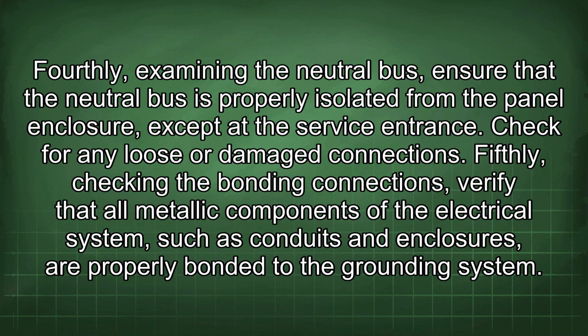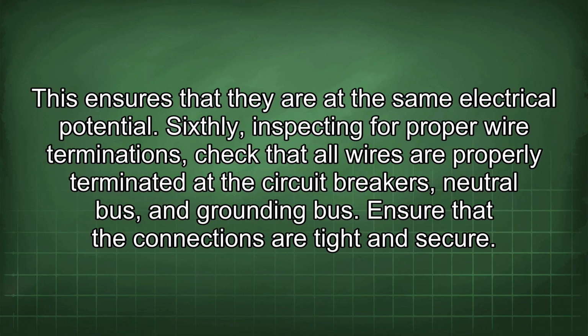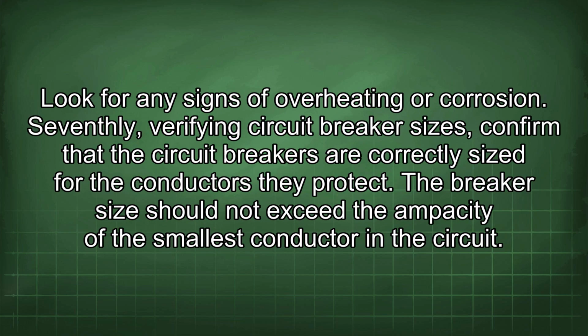Fifthly, checking the bonding connections. Verify that all metallic components of the electrical system, such as conduits and enclosures, are properly bonded to the grounding system. This ensures that they are at the same electrical potential. Sixthly, inspecting for proper wire terminations. Check that all wires are properly terminated at the circuit breakers, neutral bus, and grounding bus. Ensure that the connections are tight and secure. Look for any signs of overheating or corrosion.